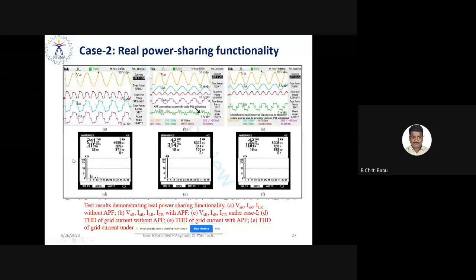Even with the control algorithm, you can see the grid current. For all the cases, the grid current THD is less than 5%. Here, this is without the shunt active power filter, and the THD is about 24.1%. But with the shunt active power filter and multifunctional inverter, the THD of the grid current is less than 5%, 4.2%. Still, the instantaneous grid current is largely reduced from 3.14 amperes to 1.66 amperes. Obviously, the losses in the inverter are largely reduced by the multifunctional inverter.